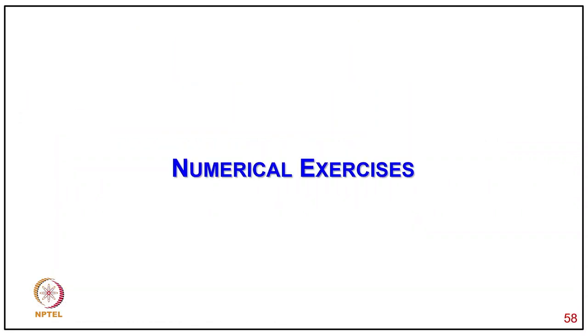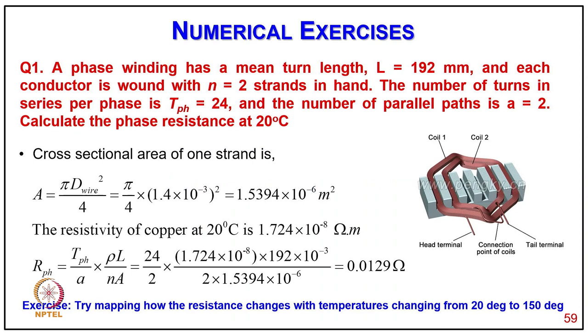Coming to numerical exercise, question 1: a phase winding has mean turn length L = 192 mm, each conductor wound with n = 2 strands in hand, number of turns in series per phase TpH = 24, and number of parallel paths a = 2. Calculate the phase resistance at 20°C. The cross-sectional area of one strand is A = πDwire²/4 = 1.5394×10⁻⁶ m². Resistivity of copper at 20°C is 1.724×10⁻⁸ Ω·m. Resistance R = (TpH/a)·(ρL/nA) = 0.0129 Ω.